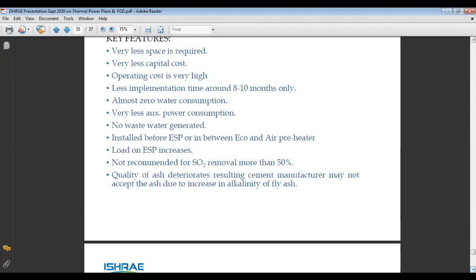Another disadvantage of this technology is the removal efficiency. The SO2 removal efficiency is very low, only 50%, compared to other technologies like the limestone based wet system, where they claim a removal efficiency of more than 99%. So it is only recommended for boilers where space is a constraint, and the plant is very old. You have to run only 4 to 5 years, and you have to comply with the MoEF norms, and the required removal efficiency is only 30-40%. Then you may go for this type of technology.